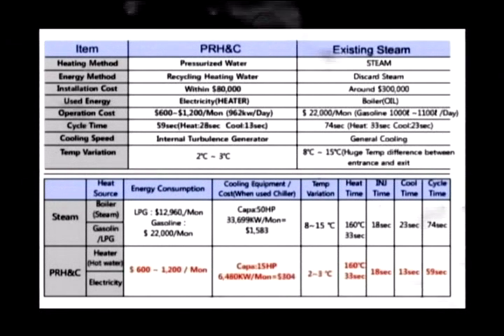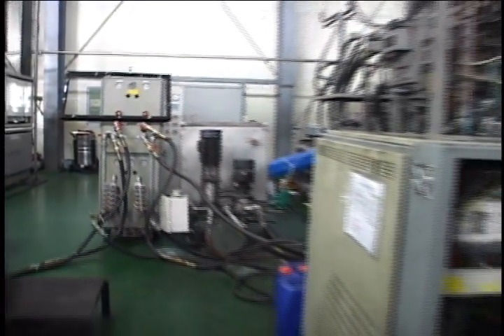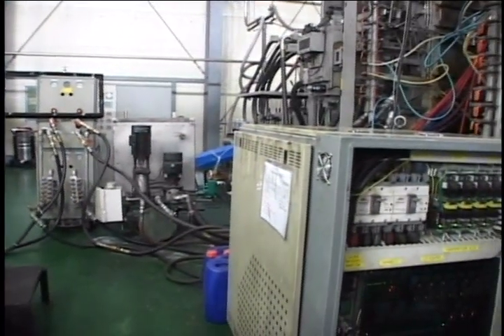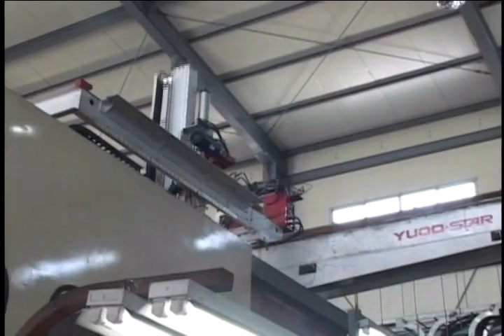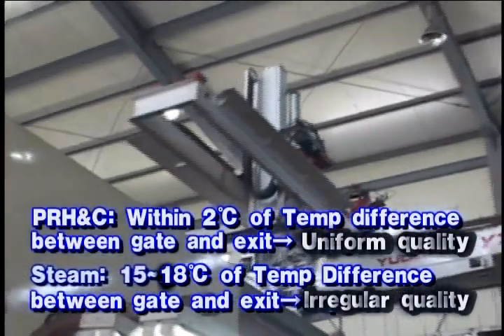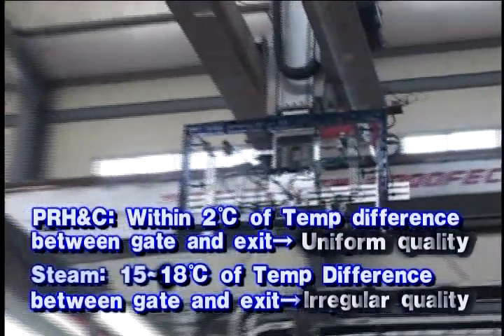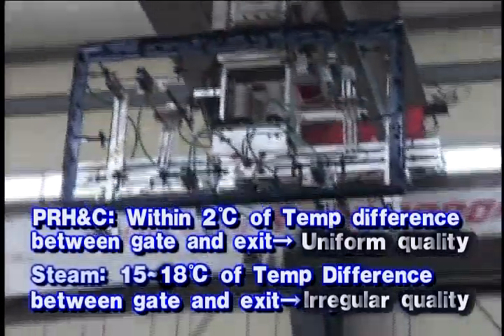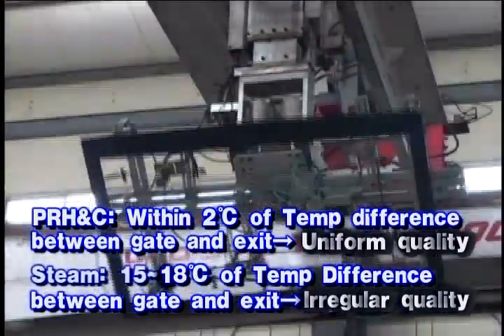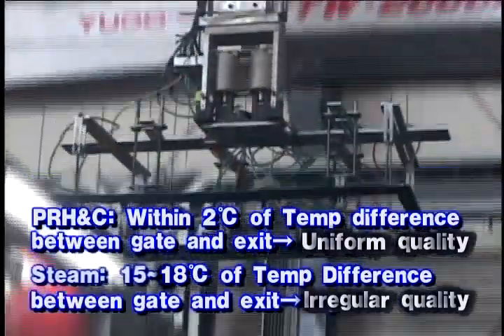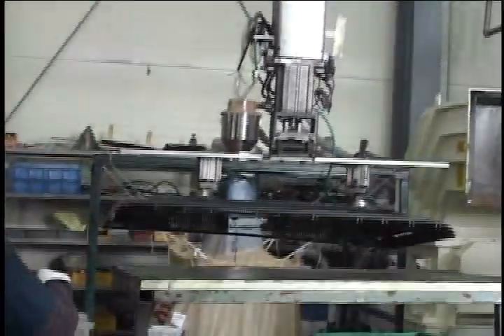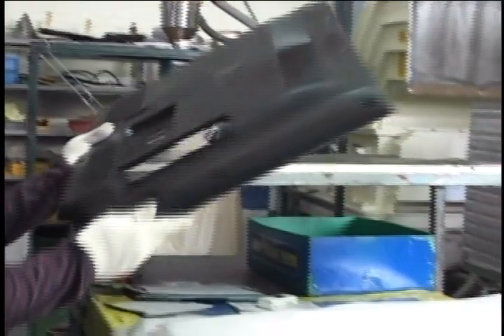This provides more stable quality than that of e-mold mounting heater on the mold. PRH&C has little temperature deviation by keeping the temperature difference between the gate and exit of mold in the range of 2 degrees. But other equipment, including steam, shows a range of temperature difference of 15 to 18 degrees. Therefore, in the quality of molding products, the difference between two methods is definite.